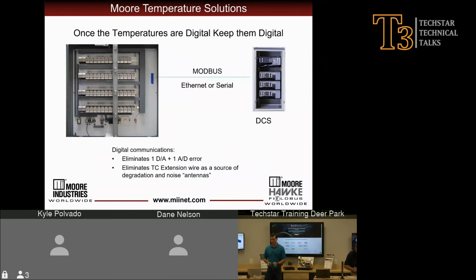from analog to digital. Modbus over Ethernet or serial is another way that we can convert our thermocouples and RTDs to digital signals. Again, thermocouple extension wire is a very low level signal and is an antenna for noise. And if not protected or not converted to a digital signal or high level signal, it will be susceptible and yield an inaccurate temperature measurement.